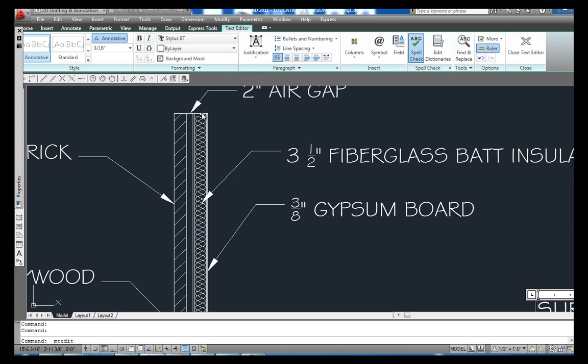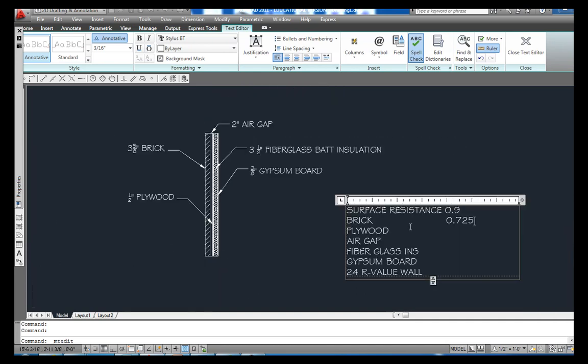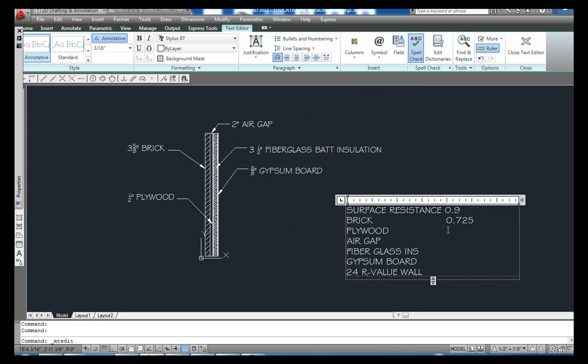But again, we get back to this 2 inch air gap. Rule of thumb is the air gap has to be at least 3/4 of an inch. And if it is 3/4 of an inch, you can consider that you have an R-value of one. And it doesn't matter if you spread this thing out five or six inches air gap, it will have just an R-value of one. So I want to come over here now and my air gap, I want to put one.